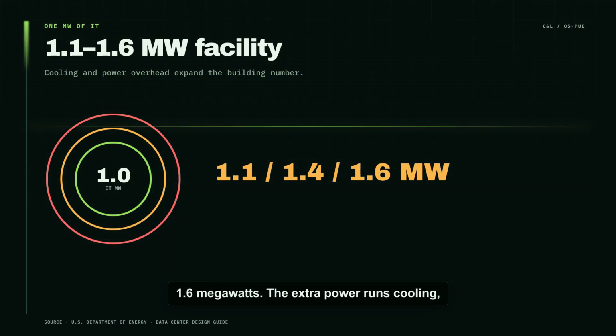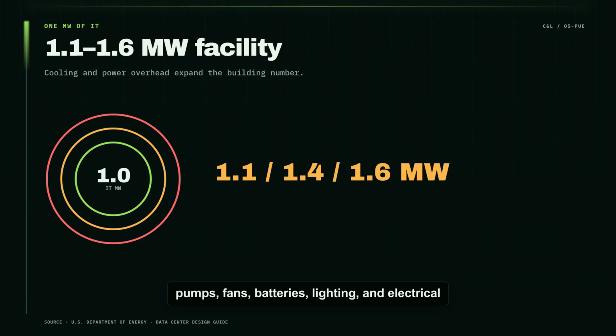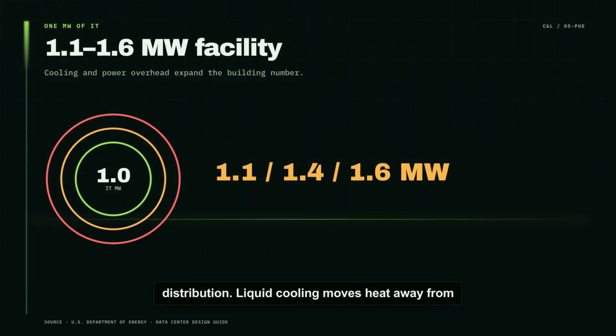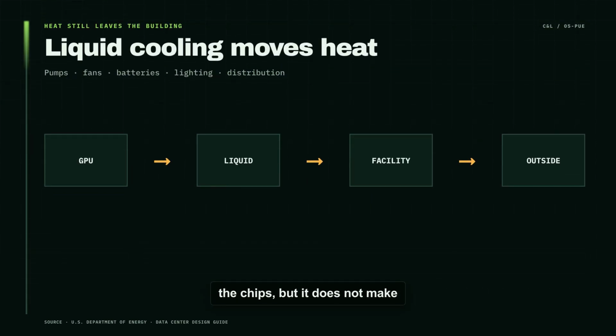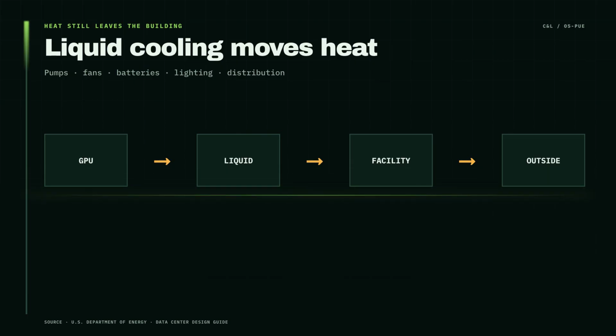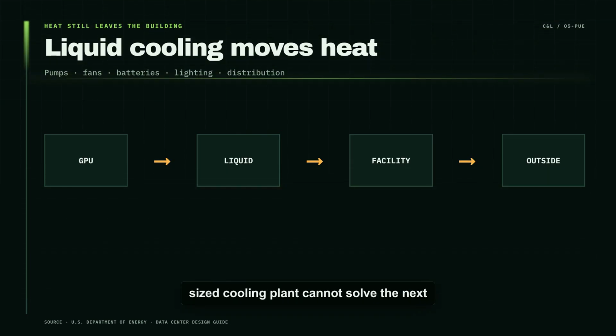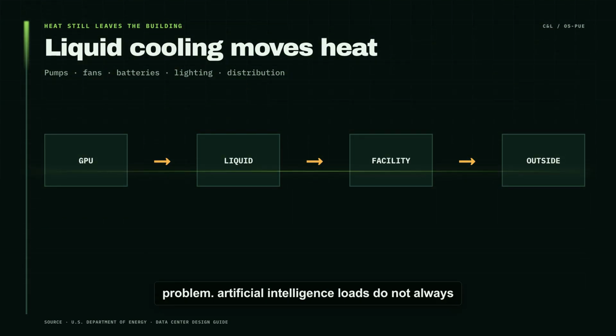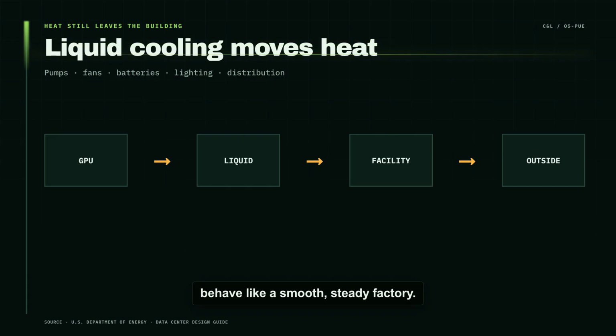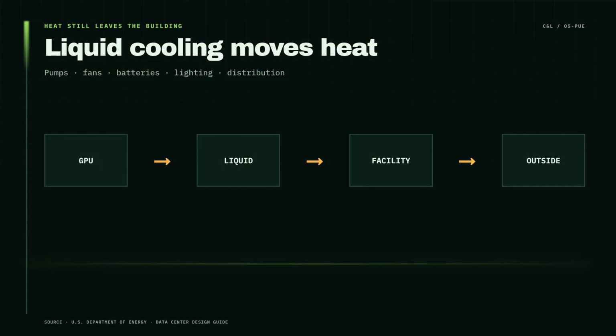The extra power runs cooling, pumps, fans, batteries, lighting, and electrical distribution. Liquid cooling moves heat away from the chips, but it does not make heat disappear. The heat still has to leave the building, and even a perfectly sized cooling plant cannot solve the next problem. Artificial intelligence loads do not always behave like a smooth, steady factory.